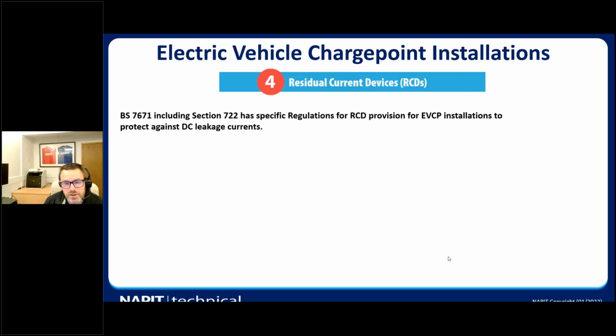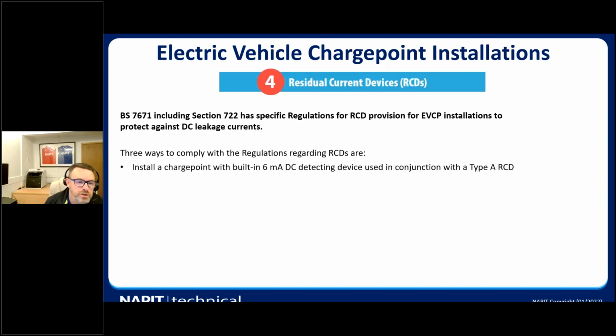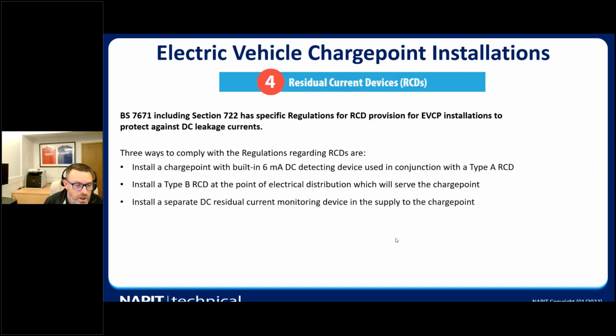Item 4 is talking about RCD devices, so residual current devices. Within BS 7671, Section 722 has specific requirements for RCD provision for EV charge points. There are 3 ways to comply with the regulations regarding RCDs. Install a charge point with a built-in 6 milliamp DC detecting device in conjunction with a Type A RCD. Install a Type B RCD at the electrical distribution point to serve a charge point. Or install a separate DC residual current monitoring device in the supply to the charge point.